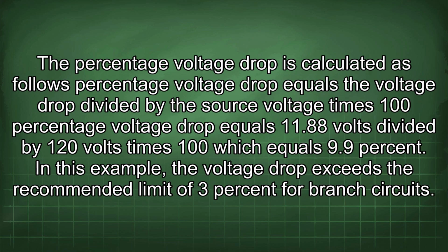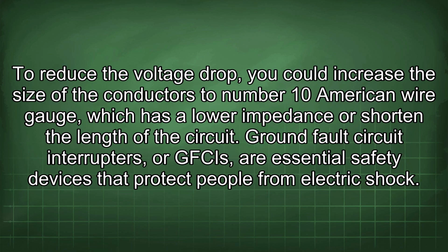The percentage voltage drop is calculated as follows: percentage voltage drop equals the voltage drop divided by the source voltage times 100. Percentage voltage drop equals 11.88 volts divided by 120 volts times 100, which equals 9.9%. In this example, the voltage drop exceeds the recommended limit of 3% for branch circuits. To reduce the voltage drop, you could increase the size of the conductors to number 10 American wire gauge, which has a lower impedance, or shorten the length of the circuit.